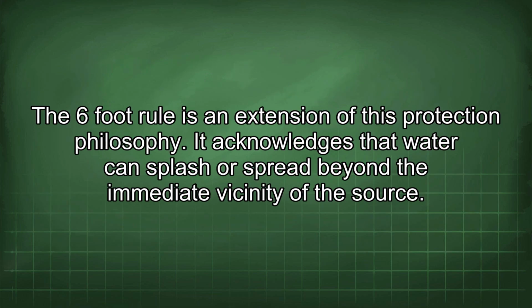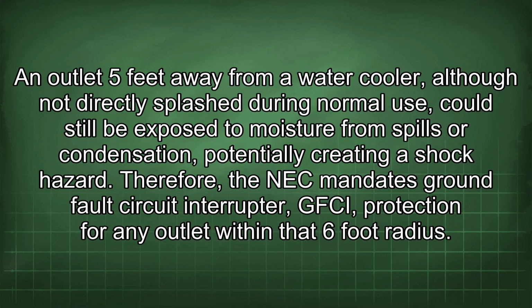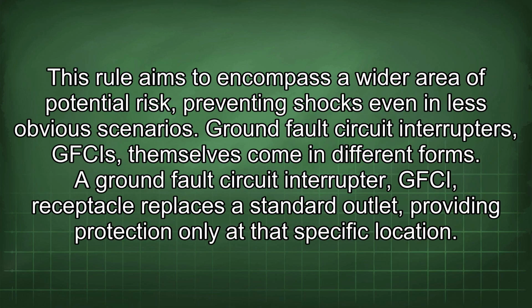The 6-foot rule is an extension of this protection philosophy. It acknowledges that water can splash or spread beyond the immediate vicinity of the source. An outlet 5 feet away from a water cooler, although not directly splashed during normal use, could still be exposed to moisture from spills or condensation, potentially creating a shock hazard. Therefore, the NEC mandates GFCI protection for any outlet within that 6-foot radius. This rule aims to encompass a wider area of potential risk, preventing shocks even in less obvious scenarios.